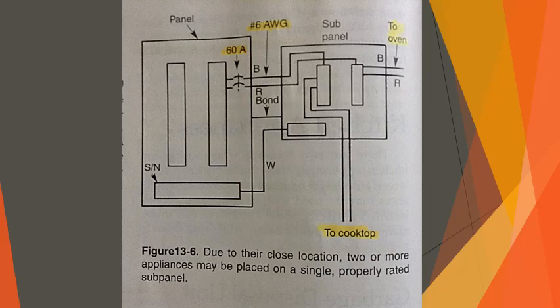Service entrance cable 8 to 10 AWG is often the method of connection, originating from the main panel or sub-panel directly to the unit. In instances where the units are close, it is permitted to connect the pair to a single circuit, providing the overcurrent protection is suitable for the combined load. See figure 13-6.